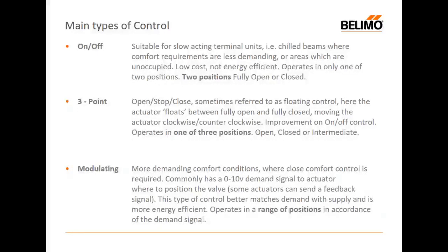And what that tends to lead to is oscillation. So when we're fully open, we have to trip that thermostat by saturating the coil and overcooling the room. That's a little bit wasteful. And then, of course, when the valve closes, it's going to take time to close. So that waste continues until it's closed. The building then rewarms itself up. And then, of course, we start the cycle again. So not terribly energy efficient, quite low cost, and not really suitable for occupied buildings where comfort is required.